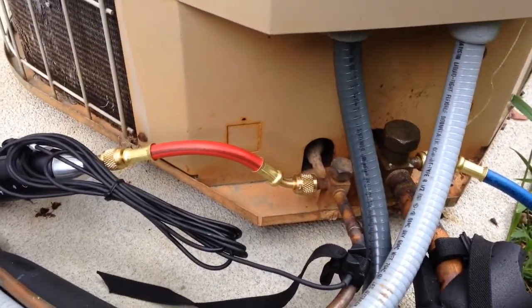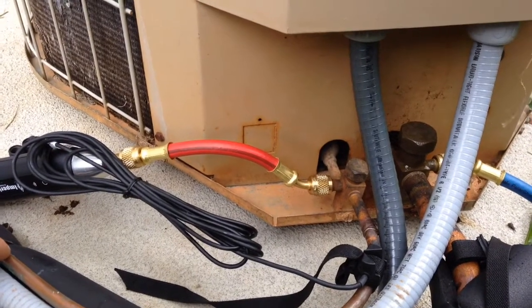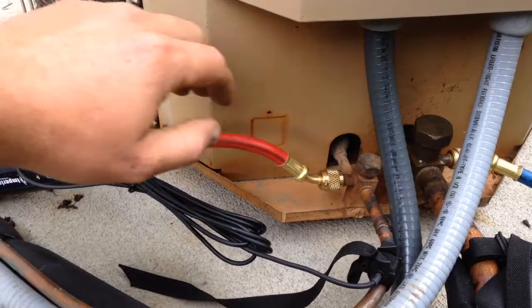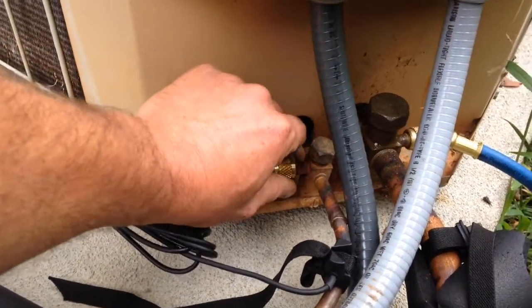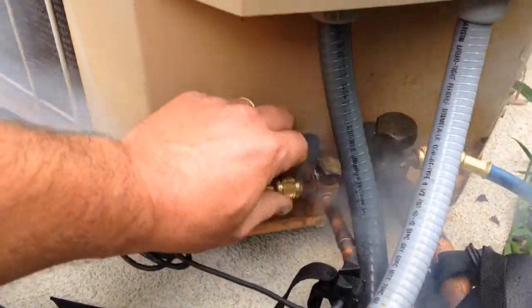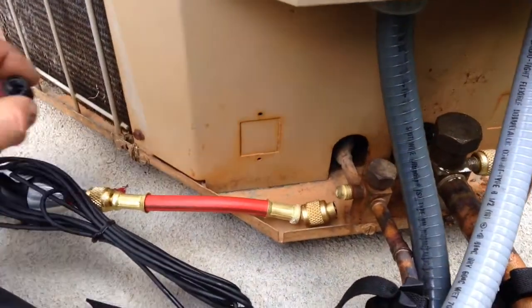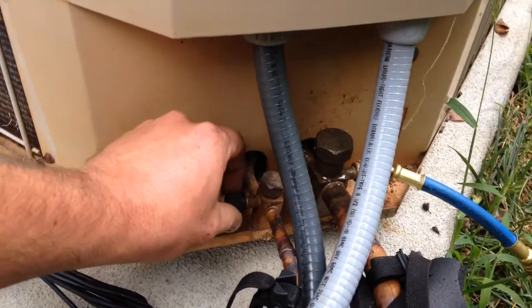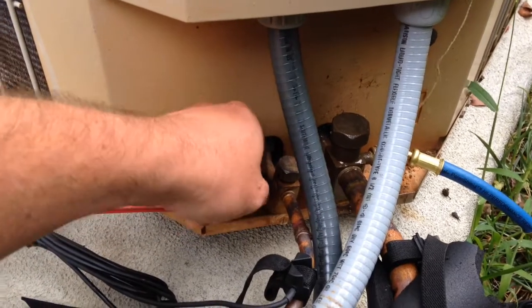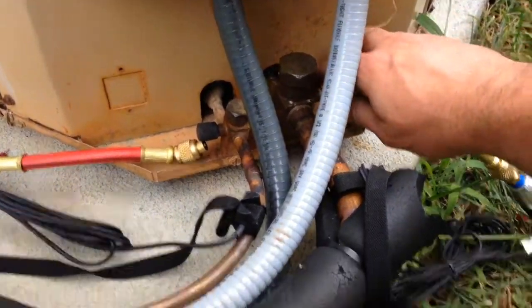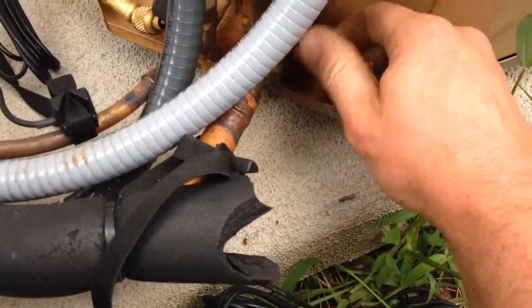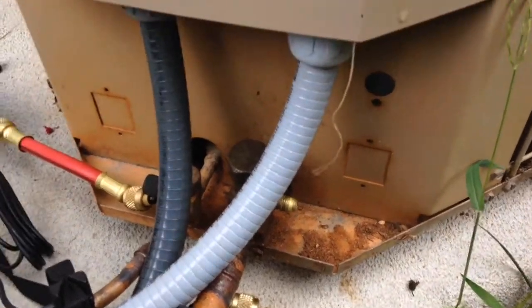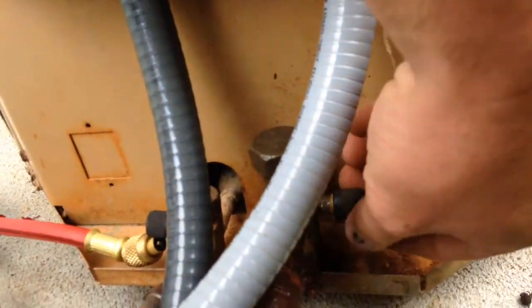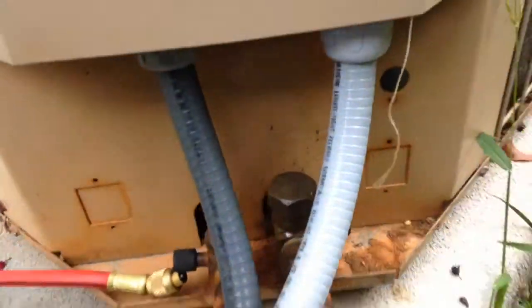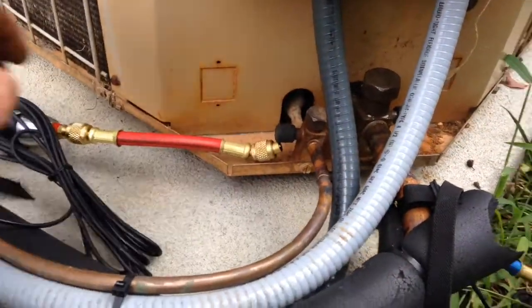so we've got the system running, and we're going to go ahead and pull the hoses off while it's got high pressure on the high side, just so you can see what kind of release we've got. Not too bad, I don't think. No worse than the 6-inch long ball valve hose connectors. Low side should be even better than that. Basically nothing on that side. So I'd say we're good to go. Release the Krakens.